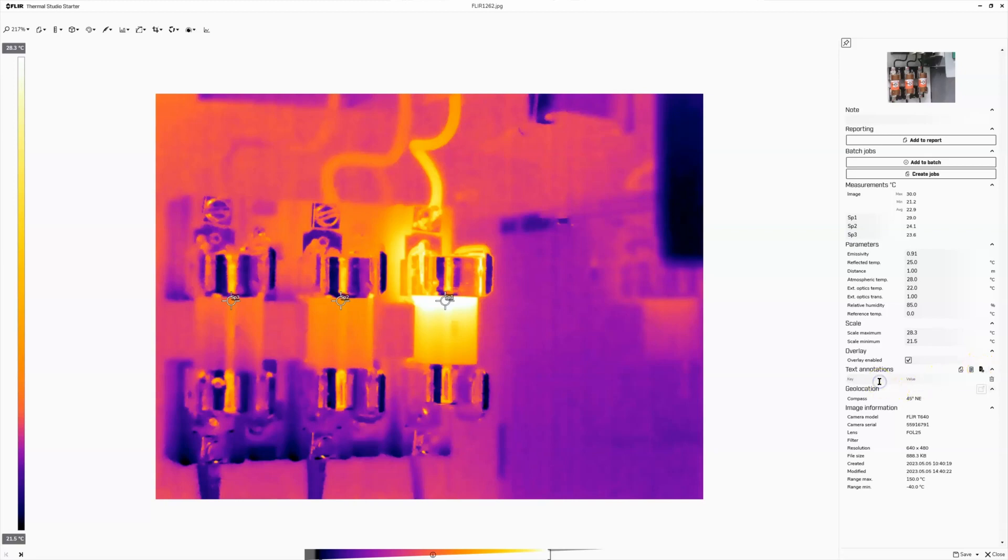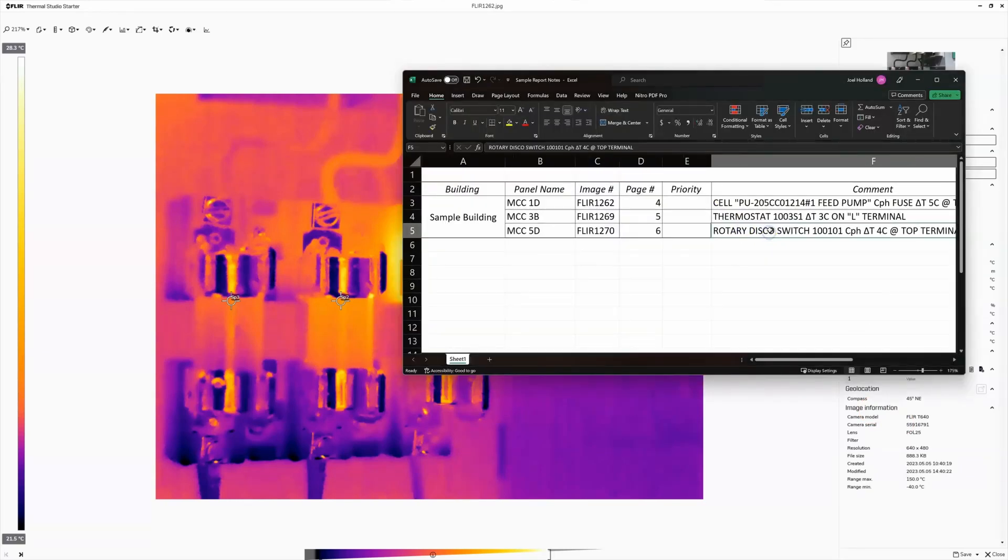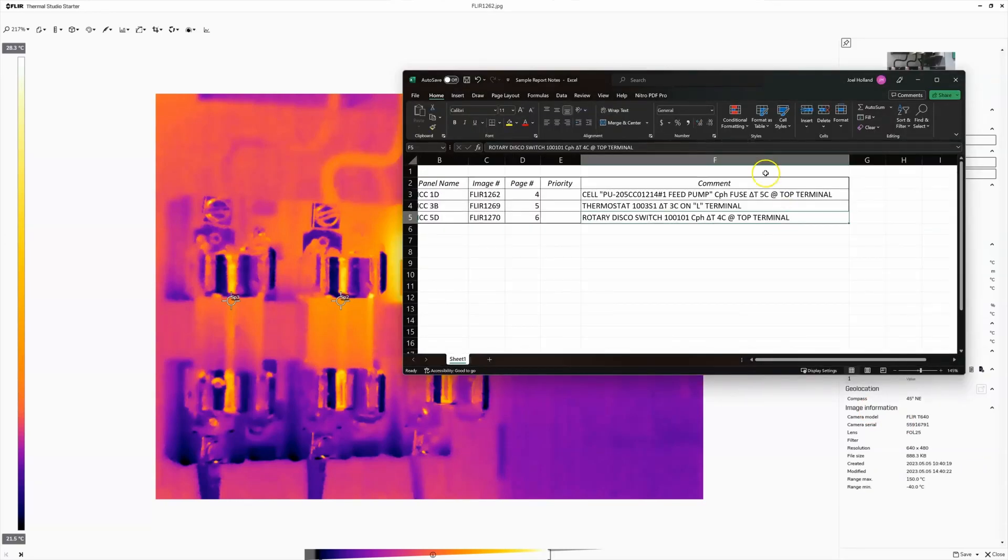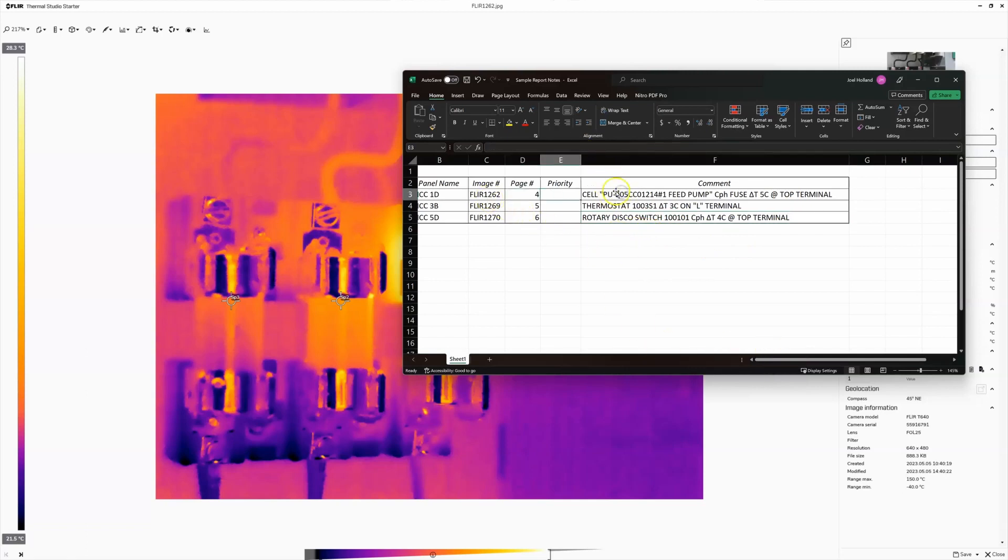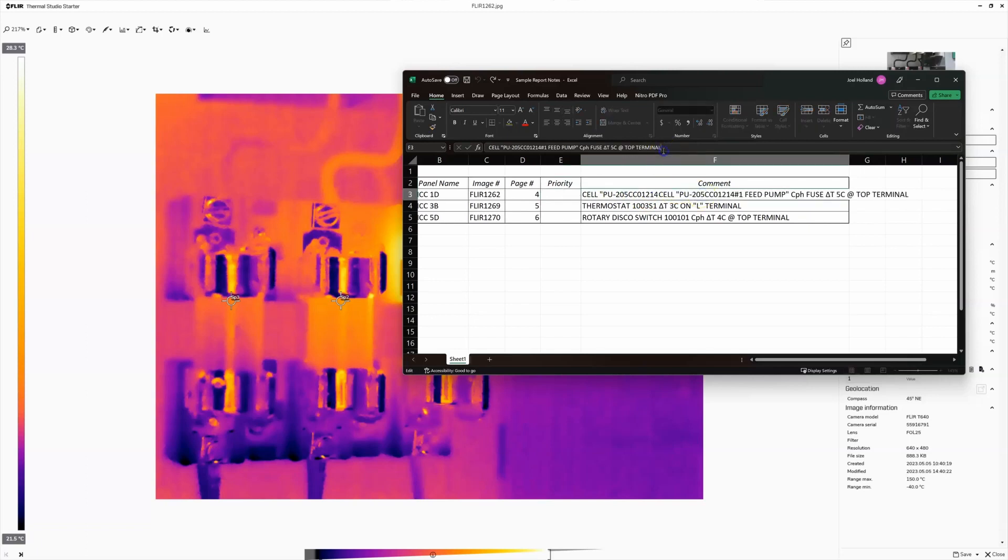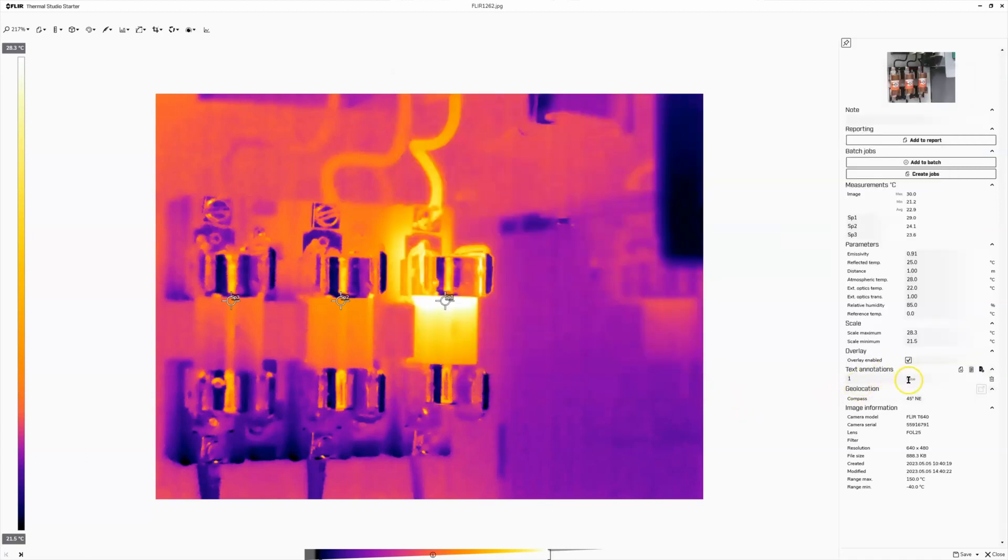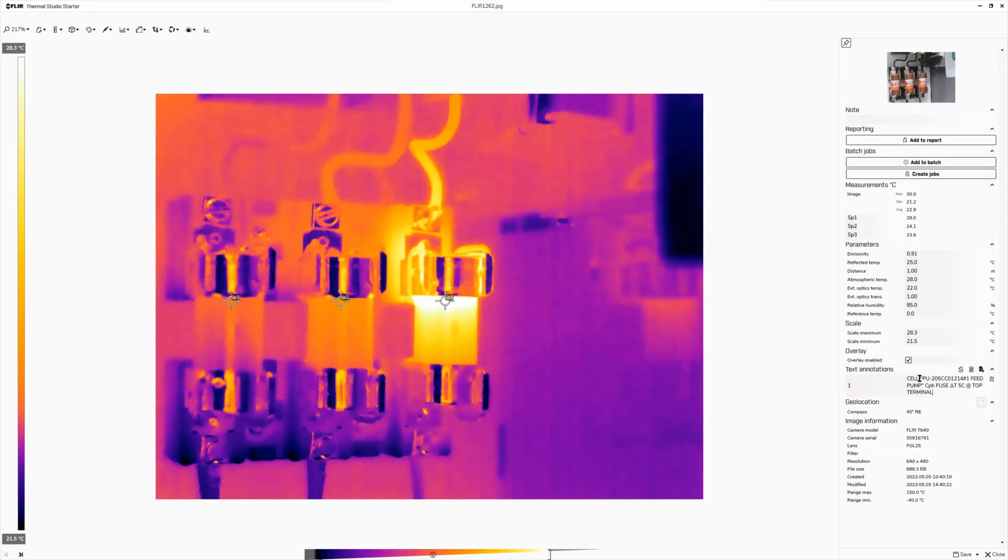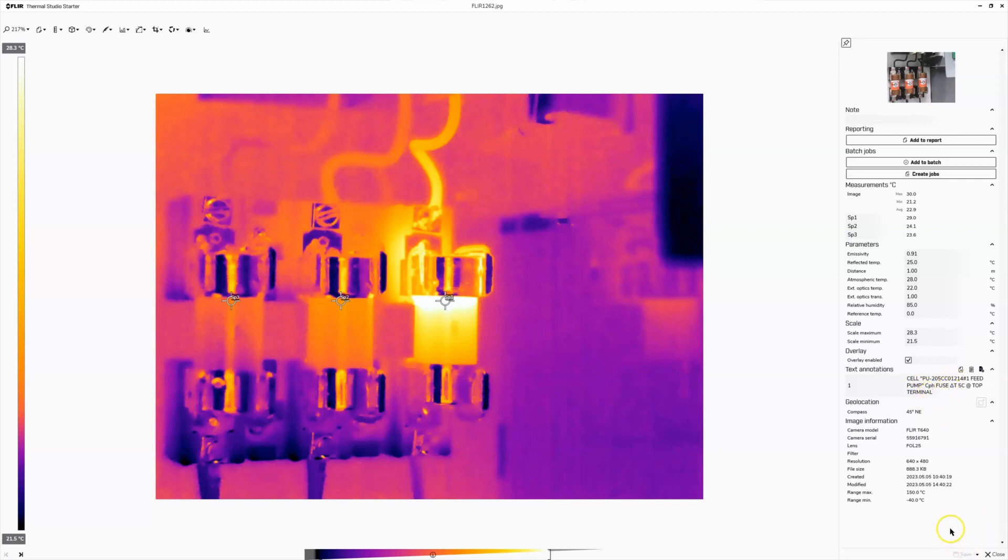For whatever reason, you always need to put a key number in. I just put one every time. And I will go back to my notes that I saved on this Excel sheet. And for this one, I'm just going to copy exactly what I said in my notes. Feed pump C phase fuse delta T of 5C at top terminal. So that sounds good to me. Now we can actually double check and see. So this is about 24 degrees. This is about 29 degrees. So my initial assumption that that was a 5C temperature difference, that looks correct. So then we're going to hit save and check this out.